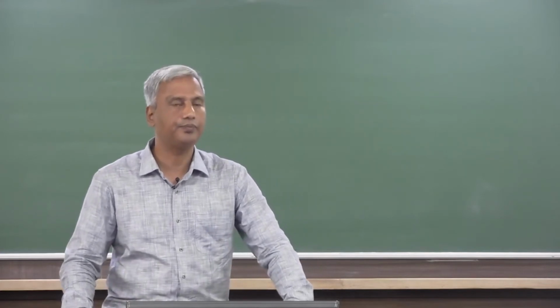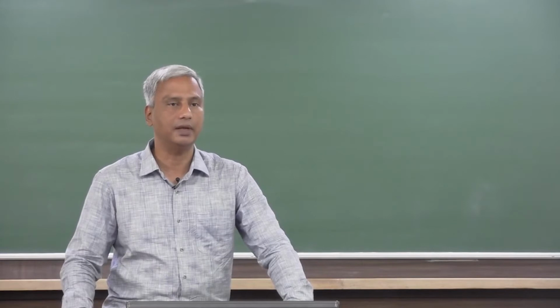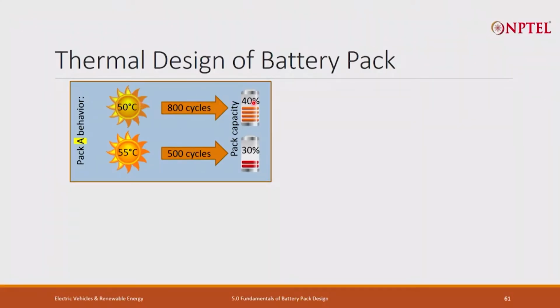Initially we have 100% capacity at 50 degrees centigrade. After 800 cycles, the pack capacity has come down to 40%. That means now the pack can take only 40% of the energy, and also it can give you only 40% of the energy. Now the same pack, when my ambient temperature is 55 degrees C...